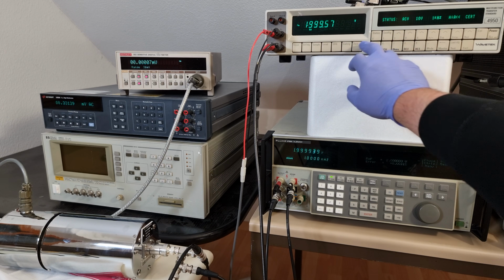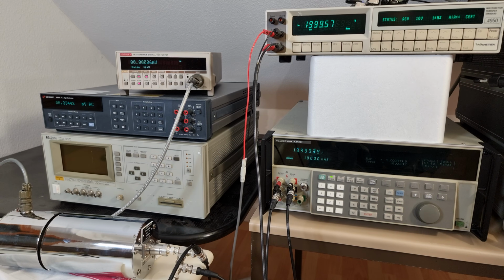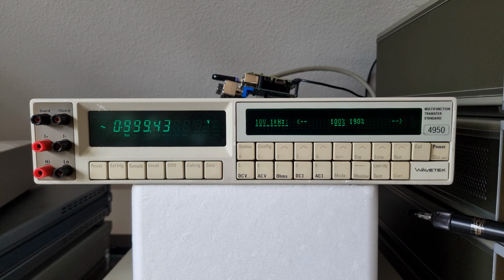The 4950 user manual doesn't specify ACV linearity at all. The closest thing we could go off of is 30-day transfer stability, which is 10 ppm of range. This is out 43 ppm of range, so not sure if it needs an adjustment. Not even sure if I could perform this adjustment if I had to.